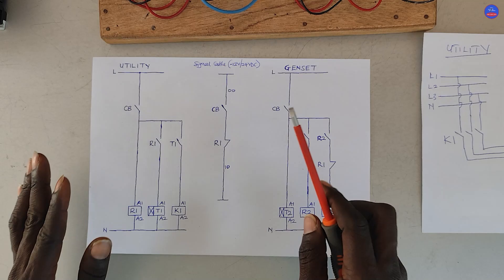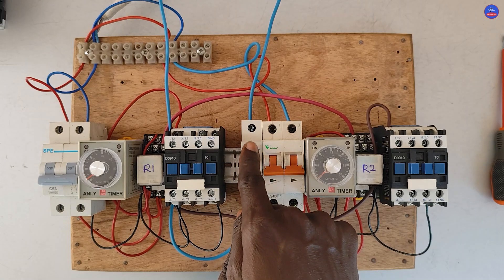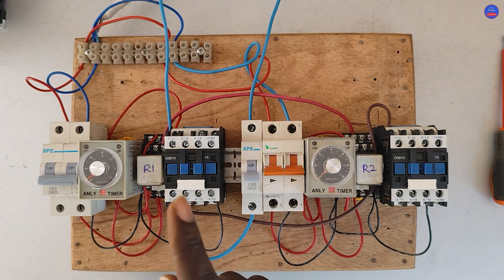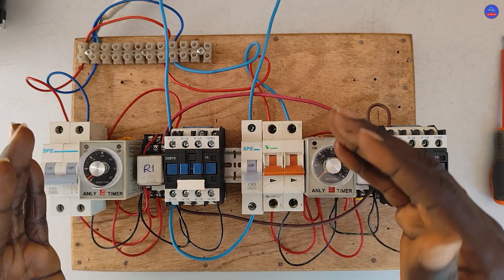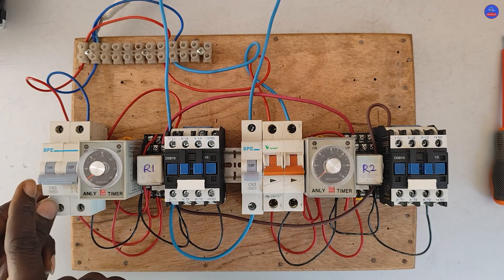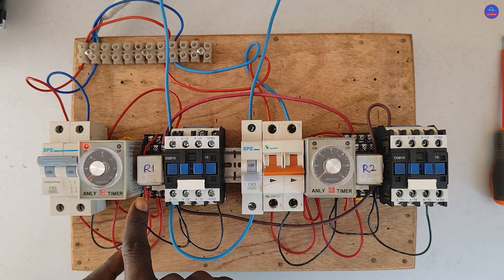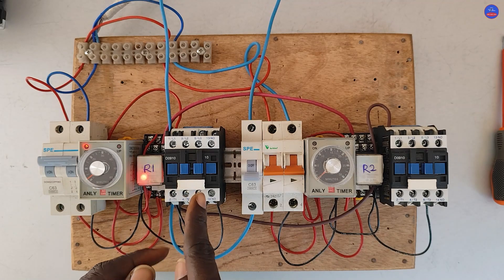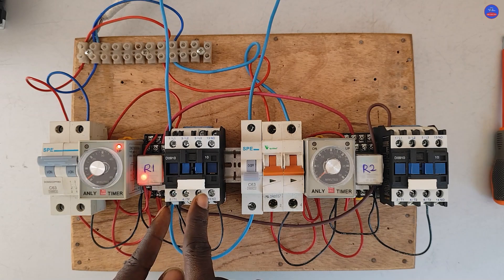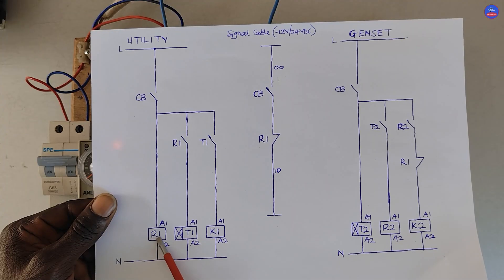So this is how automatic changeover switch works. Now let's test the wiring and see how it will operate. Right now the signal breaker is off, and at the same time the control breaker for the genset is also off. I have set the timers — you can also set it depending on how you want the switching to occur. I am turning on the control breaker for the utility power. The timer and R1 are energized. After the preset time, K1 would energize — it is energized now. These contacts have closed, so now power is at the load.